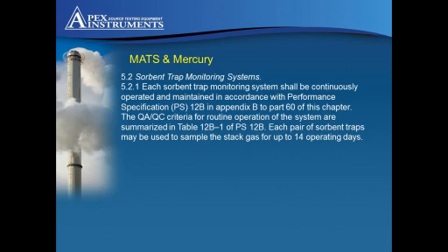However, I do want to say that in our experience, it is more common that we see sample runs of about 7 days, as PM buildup and other factors prohibit most sources from running a full 14 days on one pair of traps. So let's take a look at some of the aspects of PS12B in Appendix B that this section refers to. As a side note, PS12A, the performance specification for mercury CEMS, can also be found in Appendix B, Part 60.